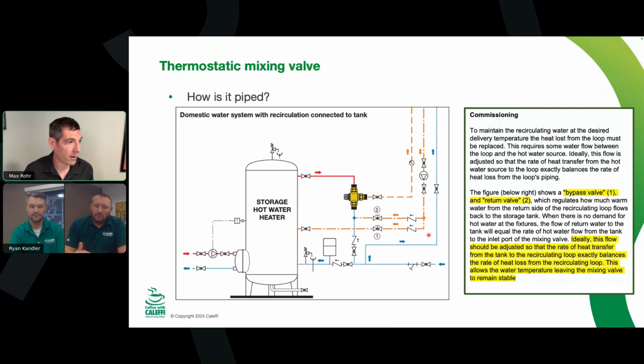Yeah, correct. Okay, then this is on the end of the recirc line. After the water is all the way back from the building, we want to mention a couple of commissioning things. When we bring the recirc line back with the thermostatic mixing valve, we want two different balancing valves. I've heard them called a bridge valve and different things like that. In the literature, we call them a bypass valve and a return valve. What we're trying to do is match the heat loss going from the mixed outlet. If we're mixing out at 113 and it's coming back at 110 in this example, none of these numbers I use are ones you should copy, you should always come up with your own numbers. It wouldn't necessarily be good Legionella management to mix out at 113, that's just for the math of this. So it's coming back at 110 degrees.